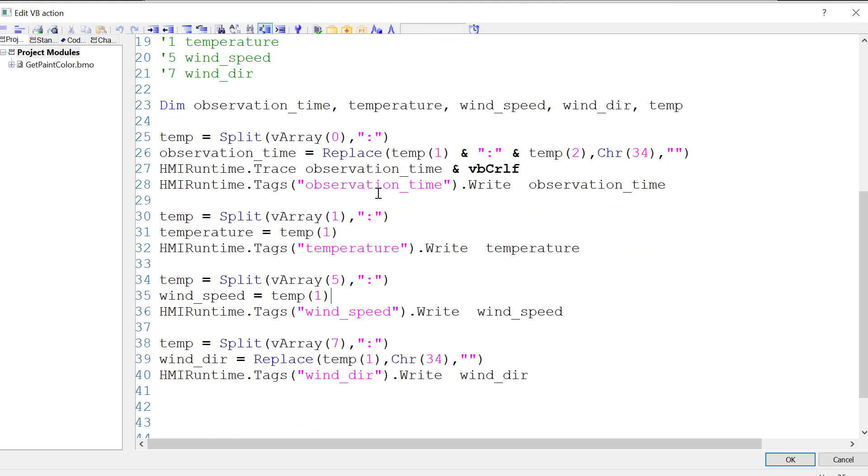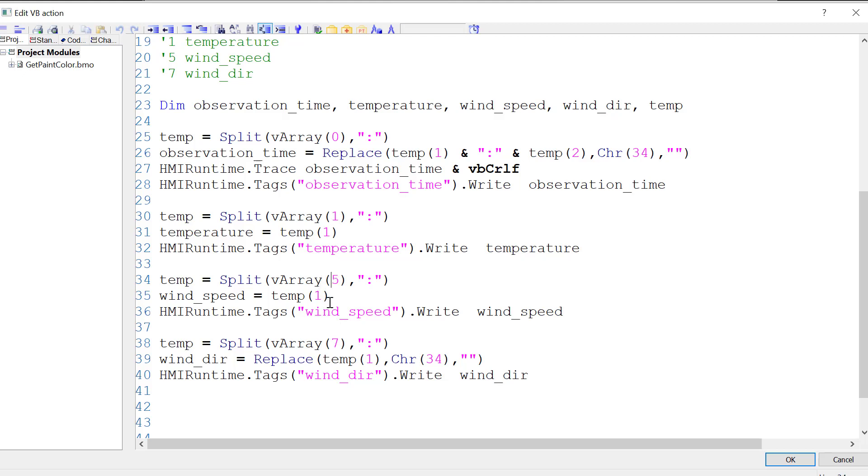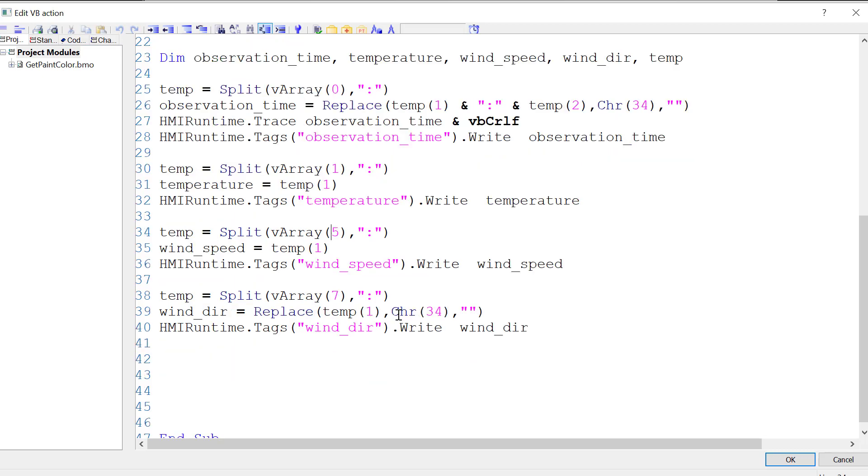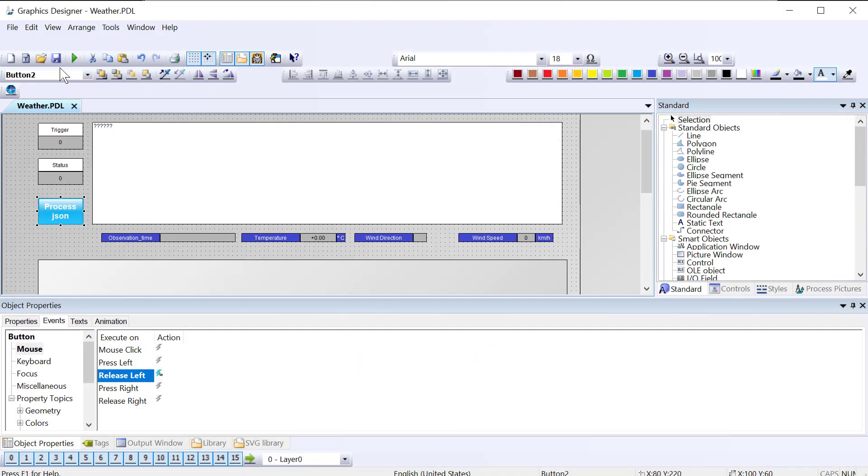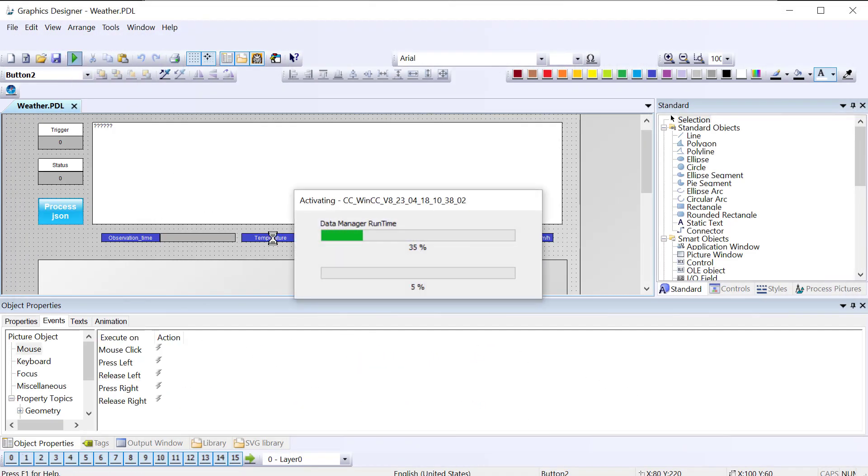For the other elements, we just have to take the second array element, which is element number 1. So I split out vArray 1, which is our temperature, write it to the tag, get element 5 of our array, split that out, write that to wind speed, do the same thing here. So we can just save this page and go to runtime.